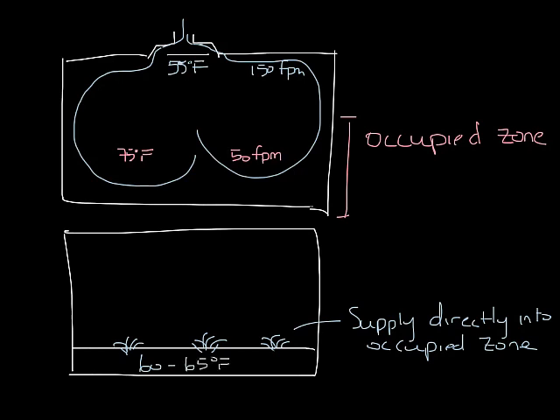Like I said, you only want to cool the occupied zone. There's no reason to pay to cool the ceiling because no one is up there. So what you end up with is a stratified layer that you don't want to break, where warm air is at the top, and somewhere in the middle, somewhere between say 4 or 5 feet, there's a stratification layer.